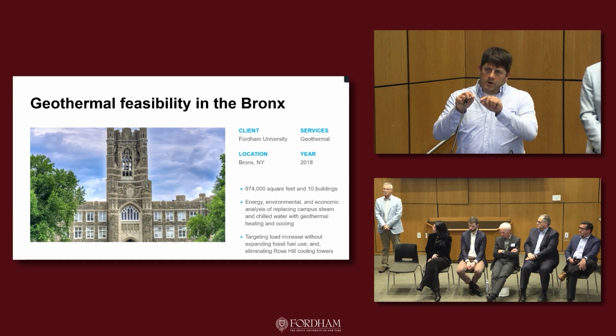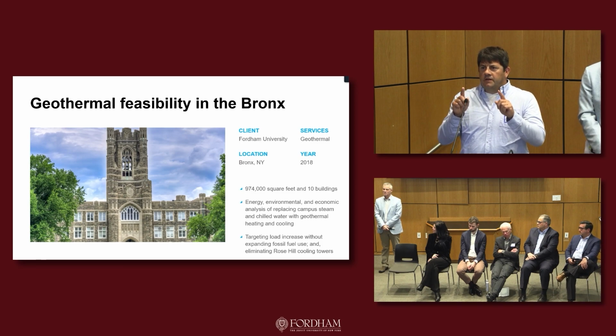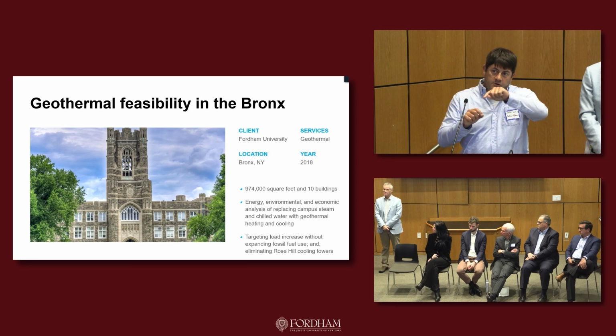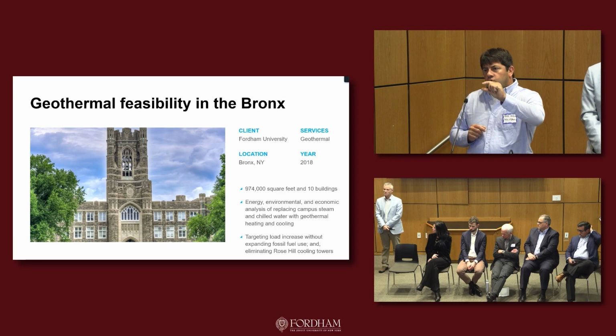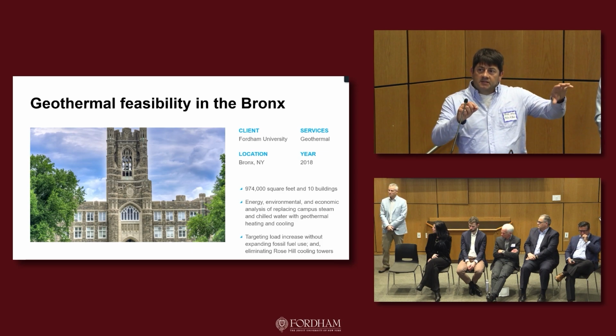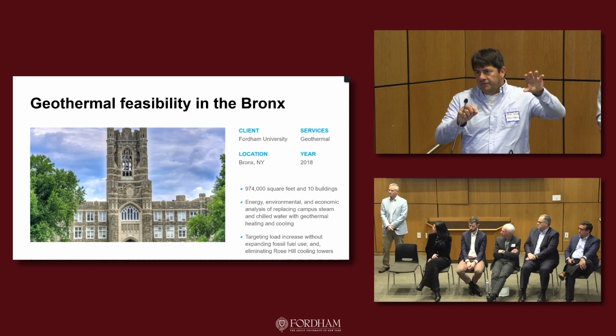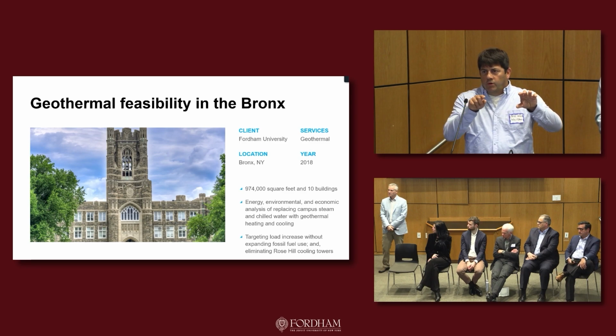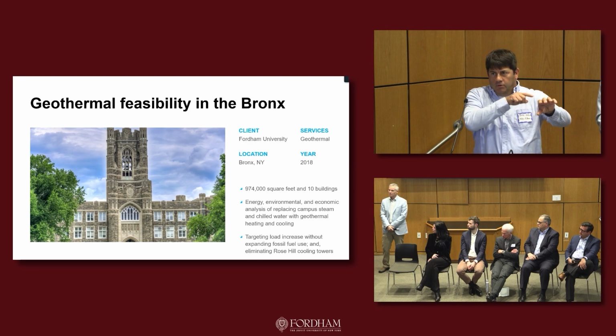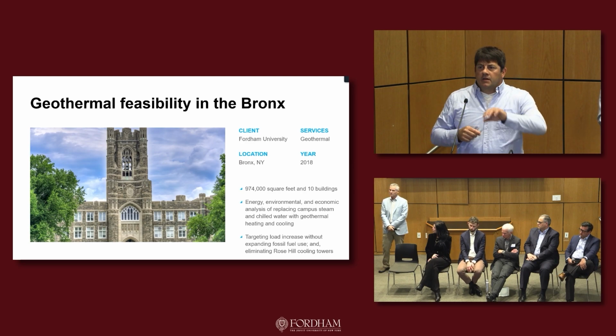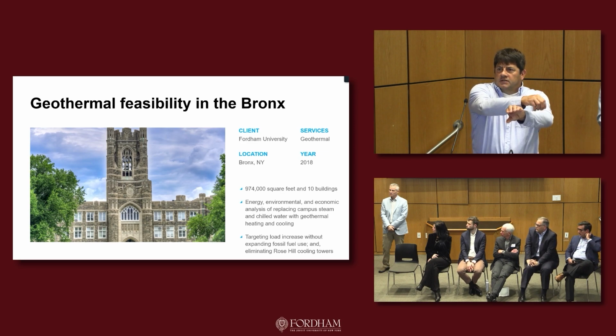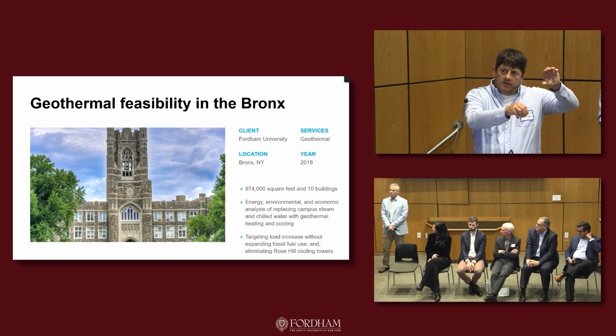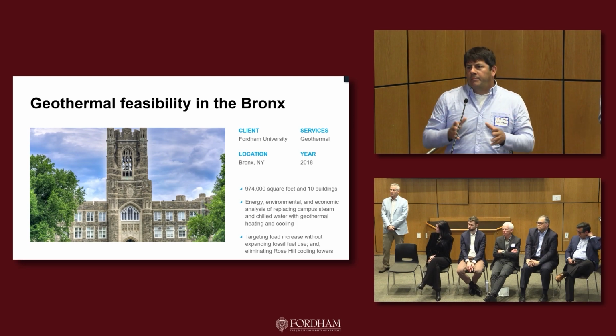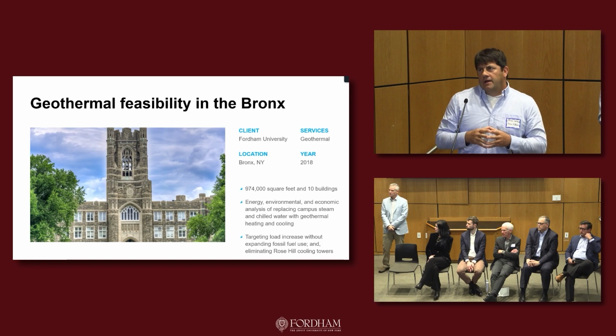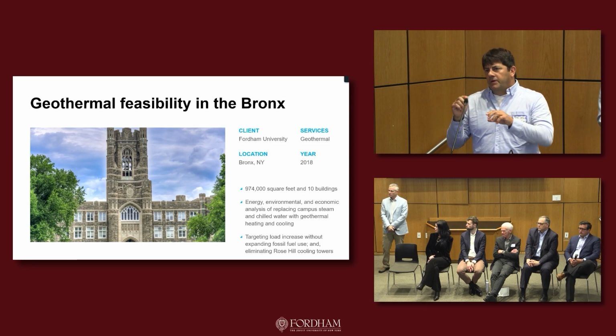But it's really about where you're injecting the energy and what is the allowable water temperature drop in your pipe. So especially in heating, you can't allow your temperature to get too cold, right? Because my next heat pump over here won't have enough energy to pull from, enough lift. So that's the key, what is my allowable water temperature drop through my whole one pipe ambient system. If it's starting to get too cold, we have to then inject some more energy here to pull that water temperature back up. Okay, so it's a great application, you just got to really understand how you size that one pipe and the flow rate.